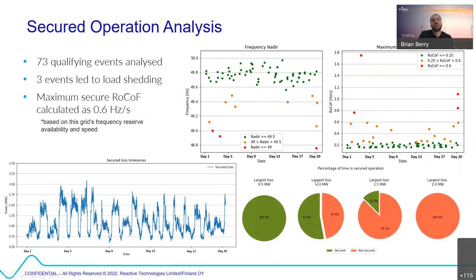The next thing is, it's all well and good to measure inertia, but what's really important is giving advice to the grid: how do we advise you on how to better run your grid? So what we did is we looked at all the events that occurred over those times. Three of these events actually led to load shedding. If you look at all of these events plotted on a frequency curve, you can see some of the ones that actually caused load shedding, these red ones down here. These are the three bad events.